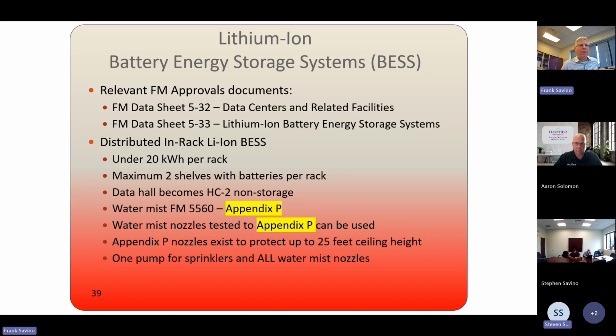Yeah. But Steve, isn't that under 20 kW per rack? Wouldn't that be for lithium? If you were doing lead acid, wouldn't it be more than that per rack? You'd never put lead acid in the rack. It's too big to get the power you need. The batteries would be bigger than the rack. And they're only doing like 1 minute of battery when they put these batteries in the rack. So if it's a 20 kW rack for 1 minute, it's 20 kW for 60 seconds as opposed to 20 kW per hour. So it's well under the requirement that they've got.